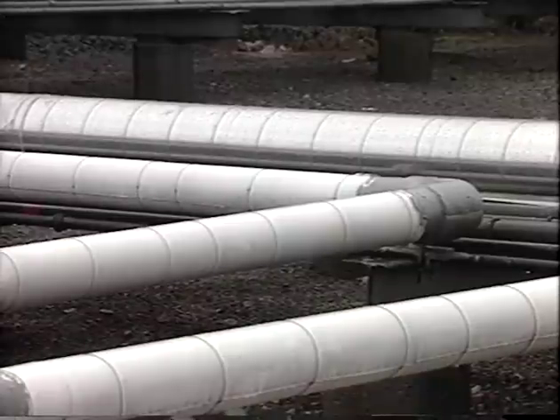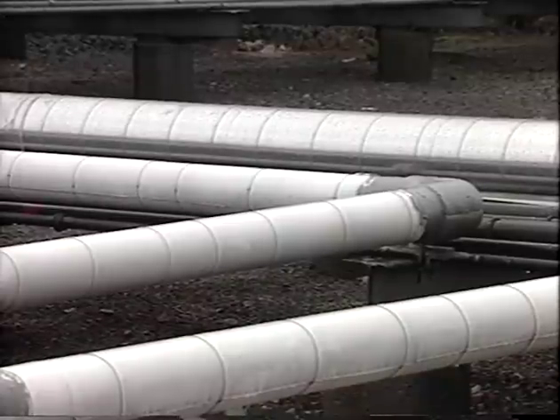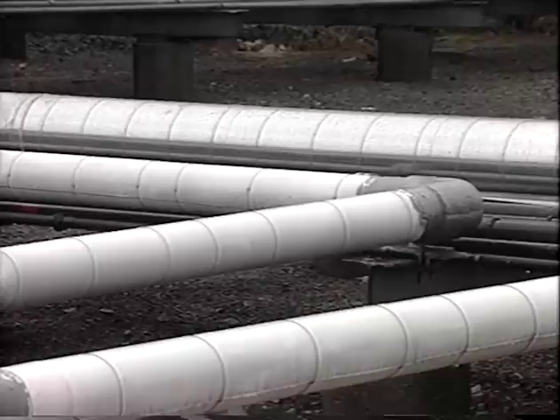And long vertical drops to the traps must be back vented. The length of the lines to traps should be minimized, and the lines may have to be insulated to reduce condensing.